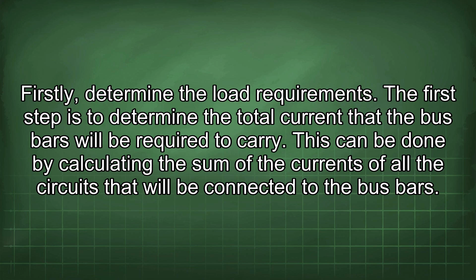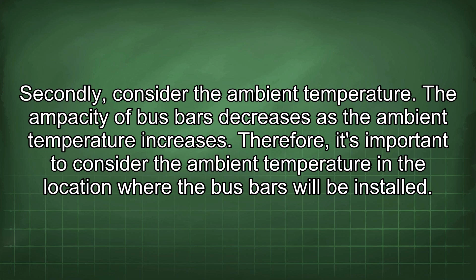Secondly, consider the ambient temperature. The ampacity of busbars decreases as the ambient temperature increases. Therefore, it's important to consider the ambient temperature in the location where the busbars will be installed.